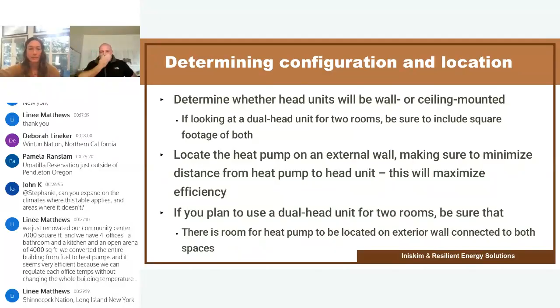So, a little bit of math fun. The heat pump capacities come in British thermal units, but you can actually calculate the equivalent in kilowatt hours. The reason you would want to do that is to calculate your savings. Our energy bills come in kilowatt hours. That's what we're billed in. So it's really helpful to understand how much these are going to use. There's just an example here.